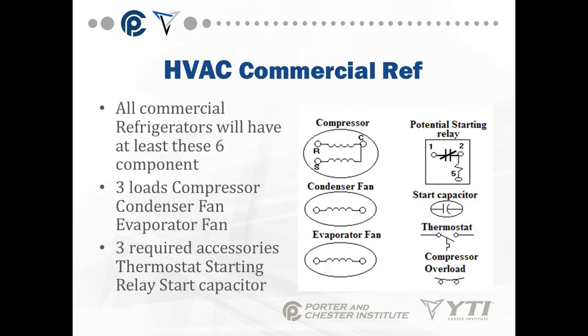All commercial refrigerators will have at least six components: a compressor, a condenser fan, an evaporator fan, some sort of starting relay, a start capacitor, a thermostat, and a compressor overload — three loads and three starting accessories.